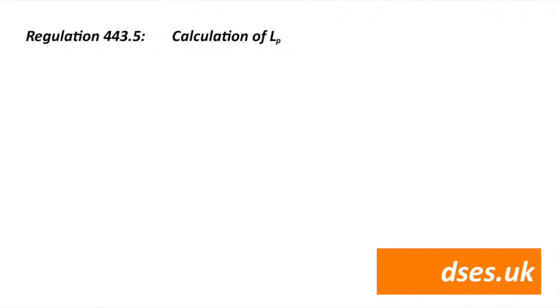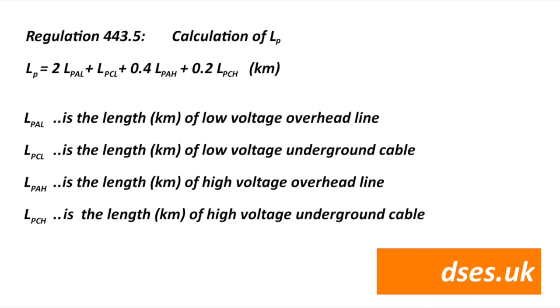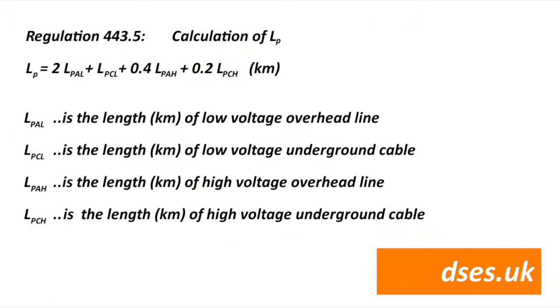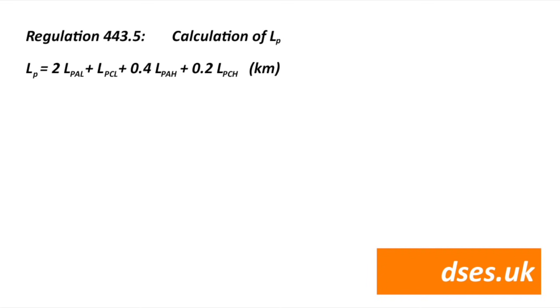Let's see, the risk assessment length LP is calculated as follows. LP equals 2 LPAL plus LPCL plus 0.4 LPAH plus 0.2 LPCH, where LPAL is the length of low voltage overhead line, LPCL is the length of low voltage underground cable, LPAH is the length of high voltage overhead line, and LPCH is the length of high voltage underground cable. Ah, Christ, I knew this was looking too easy. Well done, lads, well done. You've managed to go and pull my pants down in my moment of complacency.